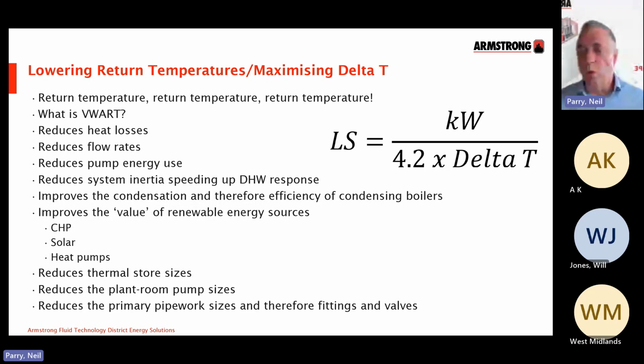And of course, the lower that return, the more your condensing boiler will condense. It's not a threshold that we need to just get over and then relax. We've done it. The more we can get that to condense, the more efficient it will be. And when we start to look at some renewable sources, let's just say solar and heat pumps here, we tend to see a flow temperature of around 50, 55 degrees. If our return temperature is 50, 55 degrees, then we can't actually add anything from that renewable energy source. Now, when we look at CHP, obviously CHP is capable of higher output temperatures, but if we have a high return temperature going back, the CHP engine itself can't get rid of its heat, and then it will have to switch off, and you lose your electricity output as well as your thermal output.